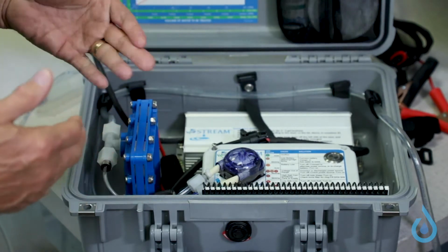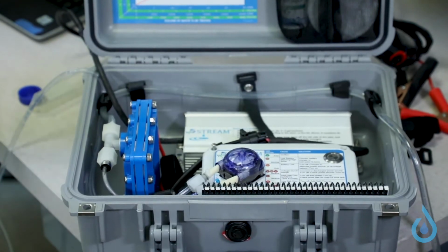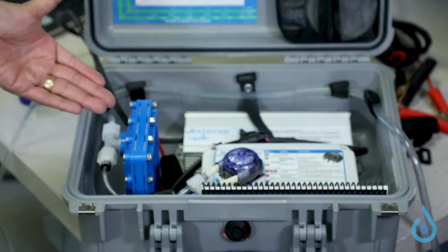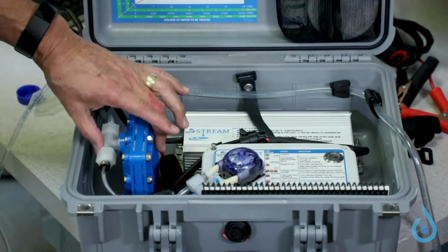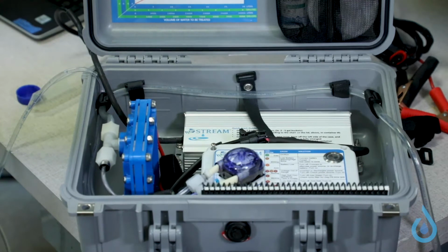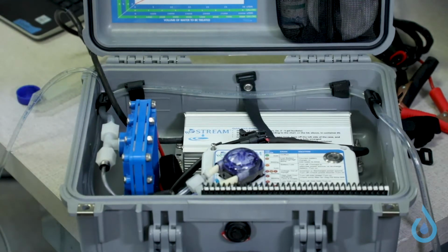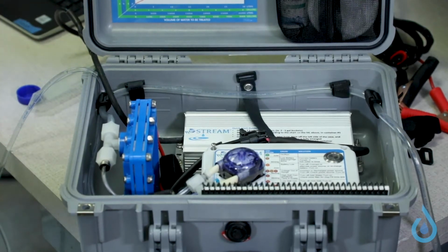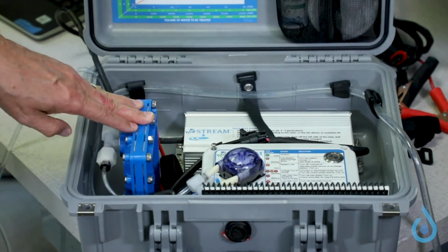One of them could happen when the brine tank is empty. It runs out of salt water, and water continues to try to be pumped through the cell. The cell begins losing volume of liquid, but amperage is still occurring on the cell. Power is still applied. So with less salt water in the cell, and it's not really circulating through the cell, it'll sit there and create a lot of heat in the disinfectant inside the cell.